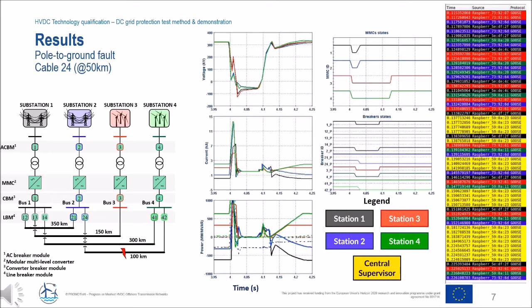HIL tests were performed using RTS models developed in HyperSIM to build up two 4-terminal HVDC networks. IEDs for protection and supervision were tested, and we could perform primary and backup sequences for different fault test scenarios. Using the IEC 61850 communication standard for these tests showed that two different pieces of hardware were able to exchange comprehensive data for the application of protection and supervision.